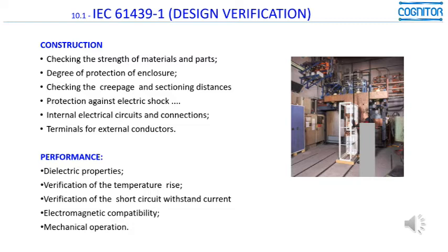Then it is extremely frequent. I would say that in the majority of the test reports that I saw up to date, you see one report which shows the test results of the temperature rise test, but there is no statement telling that the equipment was approved or not.